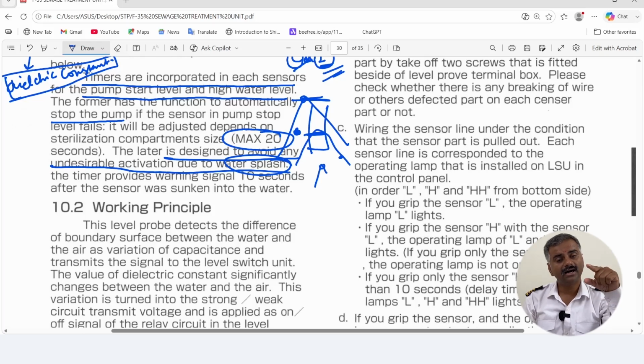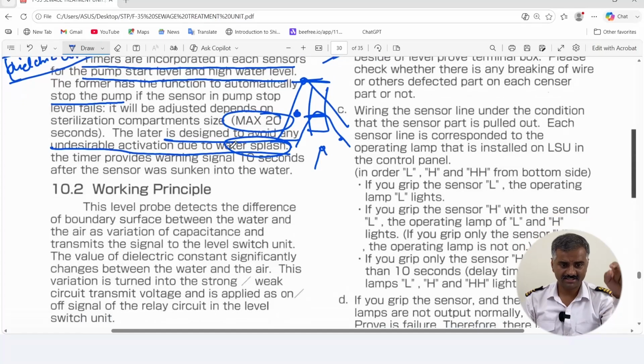Next is in case the pump unevenly does not start or stop, or the high level alarm does not come. So the timer is given so that in case of rolling and pitching, only when your sensor is dipped in water for a continuous 10 seconds will you get an alarm, or the pump will cut in and cut out. So there are two important significances of this timer. Okay, so that is what is written over here.